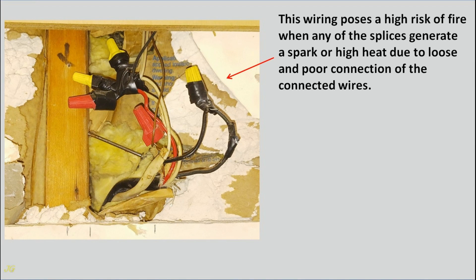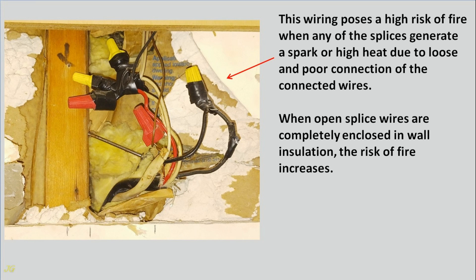This wiring poses a high risk of fire when any of the splices generate a spark or high heat due to loose and poor connection of the connected wires. When open splice wires are completely enclosed in wall insulation, the risk of fire increases.